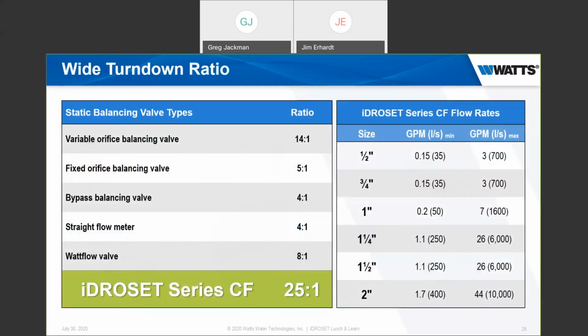You'll see on the right-hand side, the half-inch is good from 0.15 to 3 GPM. So basically, if we use 20 degrees as a delta T, that's, well, actually, no, I'm sorry, 1,500 BTUs to 30,000 BTUs. Notice the half and the 3/4 inch are really the same, because the internals are exactly the same between the two. The advantage here is that we can use a half-inch valve where normally a 3/4 might be required.